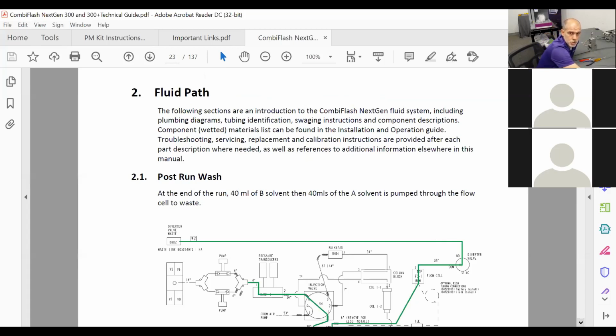If you are troubleshooting a unit that has high pressure or bad chromatography, maybe you've got a leak somewhere and you can't figure out why, this section of the manual is going to help you out tremendously. Okay, and again, you might be working on a unit when I'm at home asleep just because of time difference. So feel free, always contact me. But if you're not getting an immediate response, rely on the manual, okay? This is going to show you what you need to know.